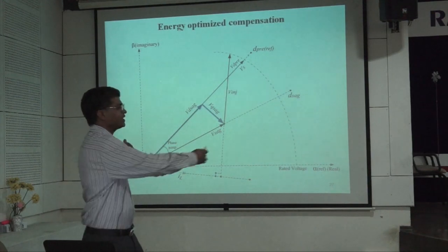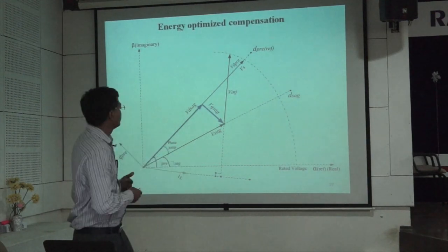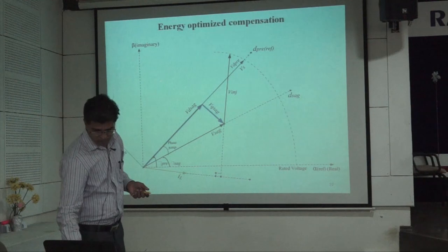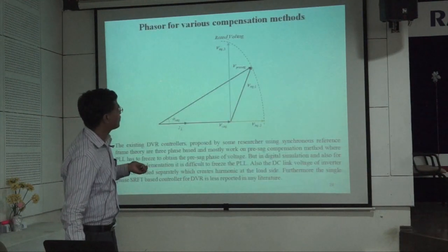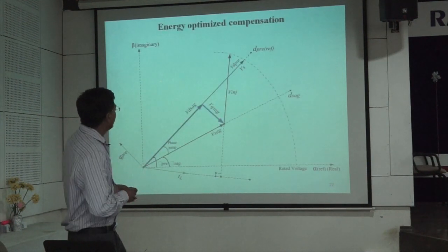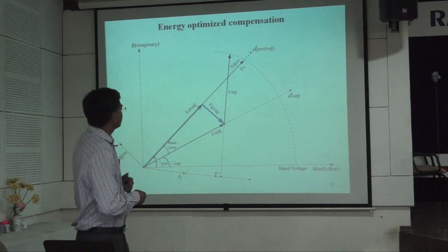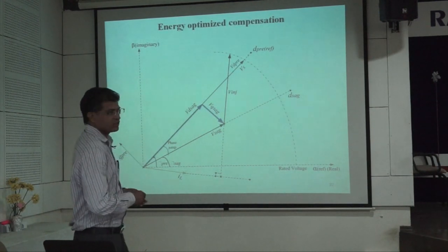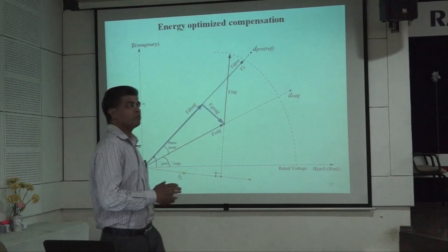So we can compensate for a longer duration of voltage sag. This type of compensation can be used for longer duration voltage sag, but it needs higher voltage injection. That's why the rating of the device required will be larger.